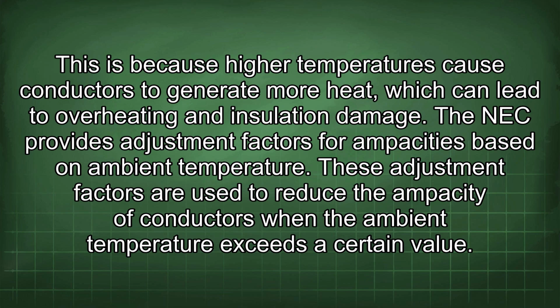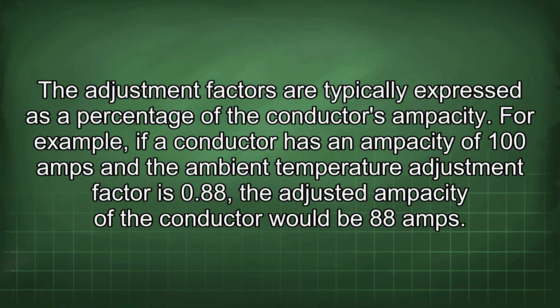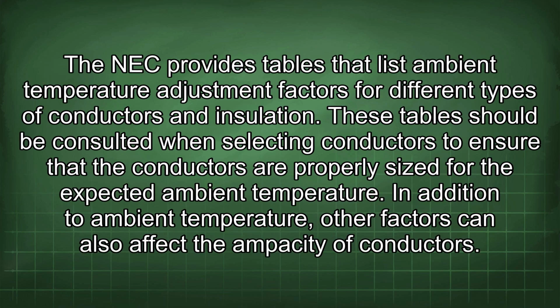The NEC provides adjustment factors for ampacities based on ambient temperature. These adjustment factors are used to reduce the ampacity of conductors when the ambient temperature exceeds a certain value. The adjustment factors are typically expressed as a percentage of the conductor's ampacity. For example, if a conductor has an ampacity of 100 amps and the ambient temperature adjustment factor is 0.88, the adjusted ampacity of the conductor would be 88 amps. The NEC provides tables that list ambient temperature adjustment factors for different types of conductors and insulation. These tables should be consulted when selecting conductors to ensure that the conductors are properly sized for the expected ambient temperature.